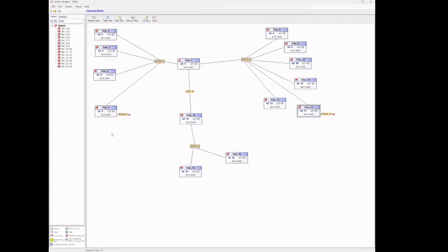So basically, what happens is if site 5 has data to send to site 12, and it can't get through on RS-Link 2, it will then attempt to make contact with site 12 on whatever ports it knows about, whatever ports have been configured. So ports that are in the network table, ports that are configured on the local RTU, it will work through each port sequentially until it gets a reply, and this happens 3 times. It's what we call retries. Now it's not ideal because it does take up system time.